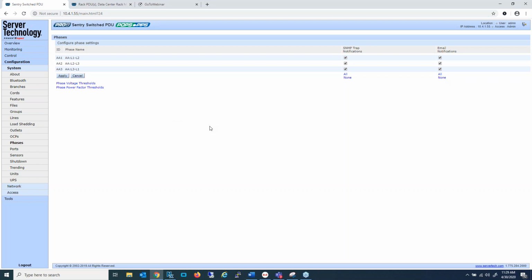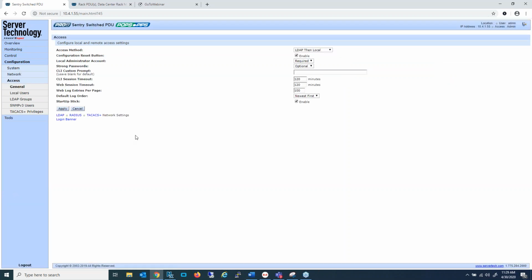That's the ideal objective, to reorganize where things are plugged in to balance the loads and therefore not get those alerts anymore. But if you just want to avoid getting those alerts, you can change the percentage or disable it. I'm actually searching. I haven't looked for that feature for a while, but it is here somewhere. Because the default is 20%, you could simply raise that percentage.